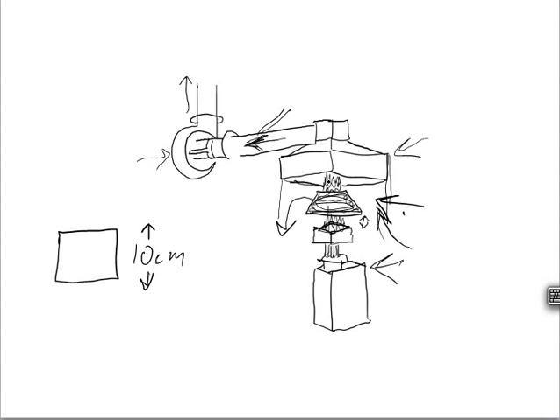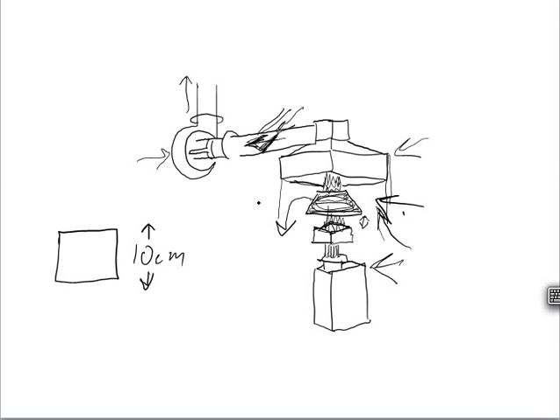And usually you're measuring mass loss, CO, CO generation, CO2 generation, soot. You have, there's a laser that shines through this flue here, and you measure the obscuration coming through the duct to get your, how much soot is being generated by the burning sample.